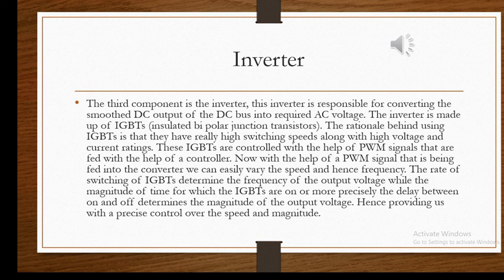These IGBTs are controlled with the help of PWM signals that are fed with the help of a controller. Now, with the help of a PWM signal being fed into the inverter, we can easily vary the speed and hence the frequency. The rate of switching of IGBTs determines the frequency of the output voltage, while the time for which the IGBTs are on, or more precisely, the delay between the on and off, determines the magnitude of the output voltage, hence providing us precise control over the speed of the motor.